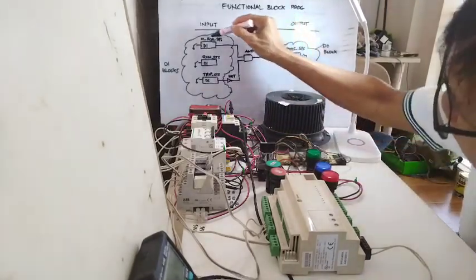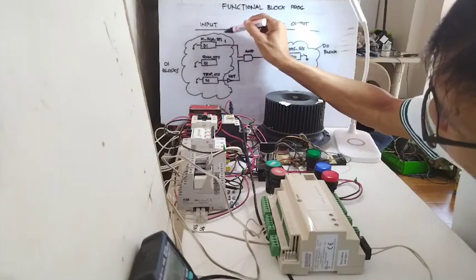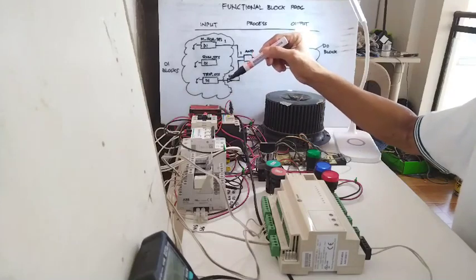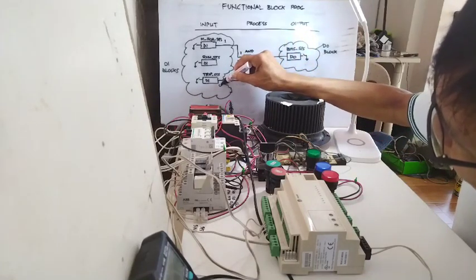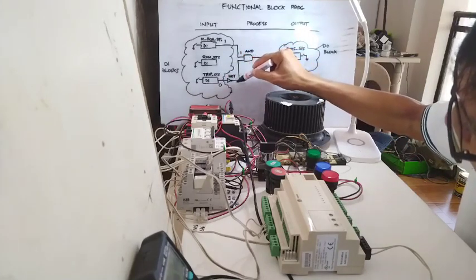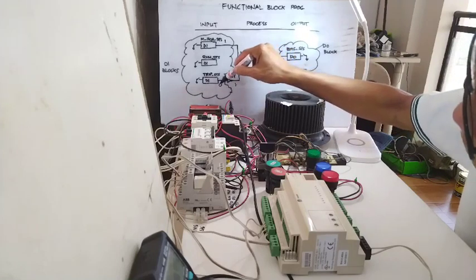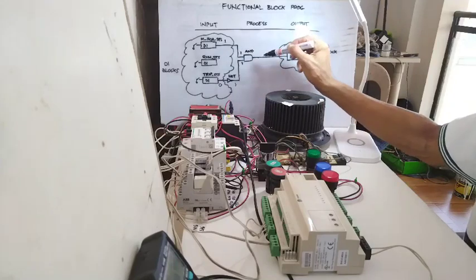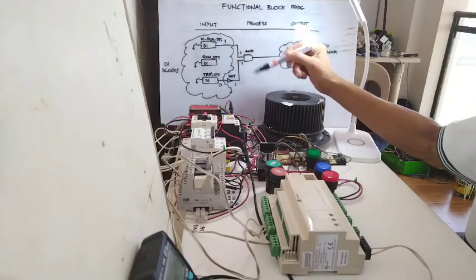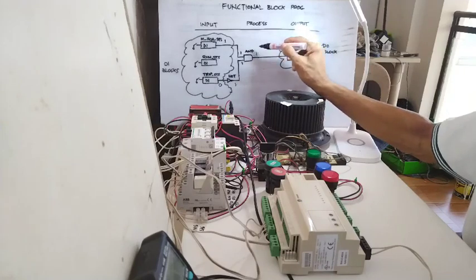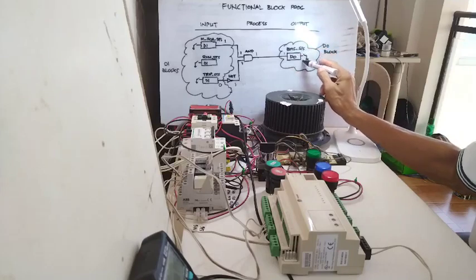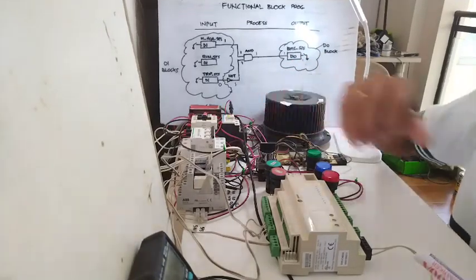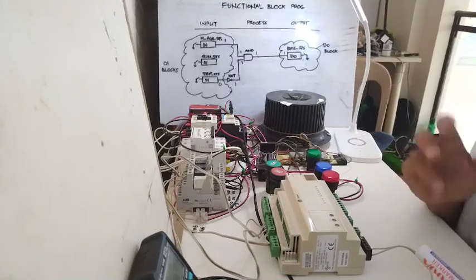Let's trace the signal. Someone puts it in auto, so this input becomes 1. There should be no trip before I can start the motor, so the trip input is 0. It goes to the NOT gate and becomes 1. In the AND gate truth table, both inputs are 1, so the output becomes 1. The contact closes, the signal goes to the control panel, the BMS start/stop provision closes, and the motor starts.